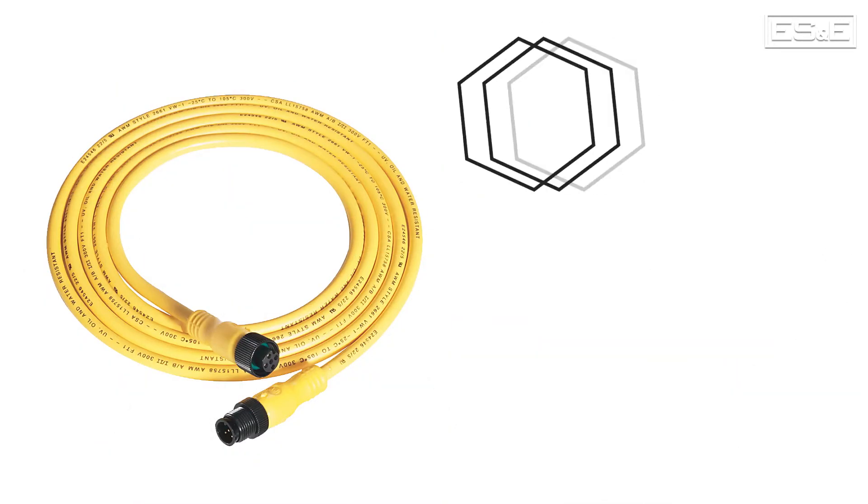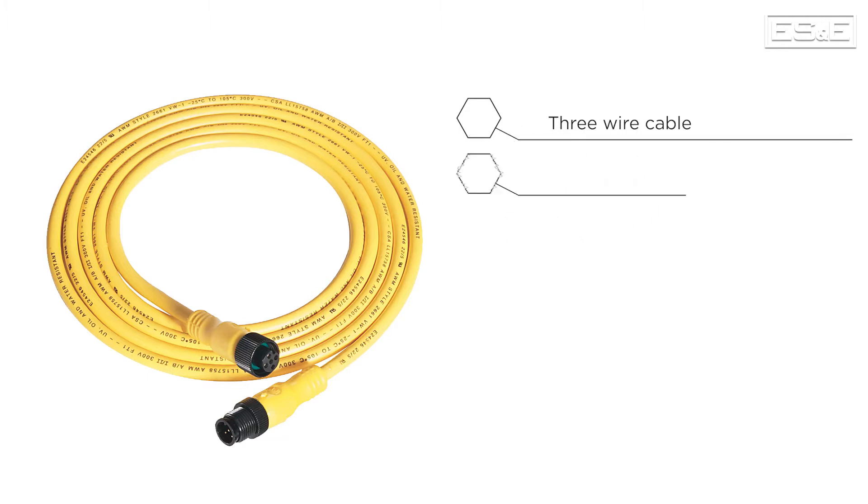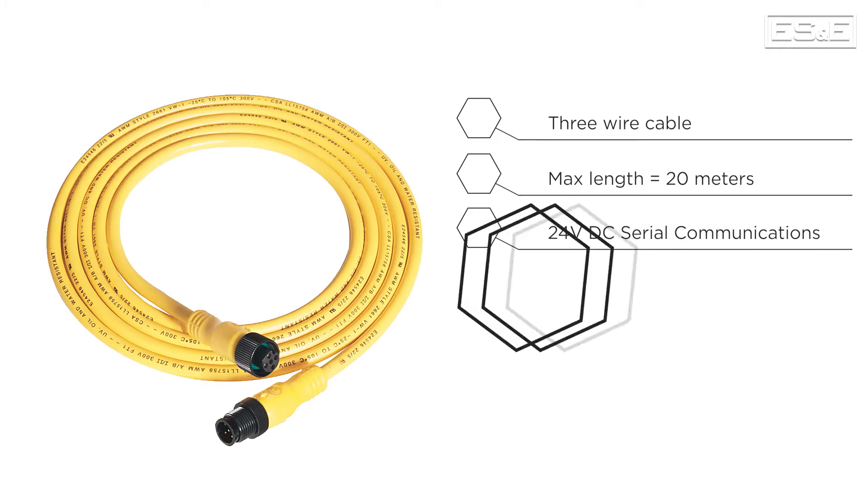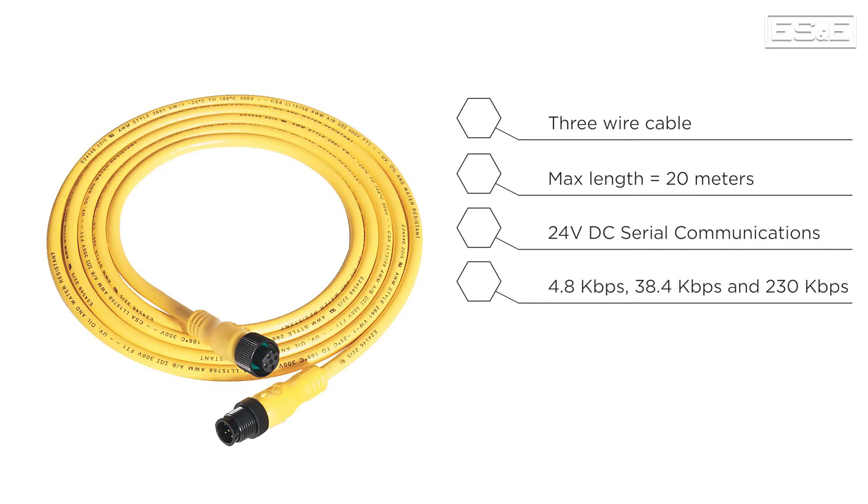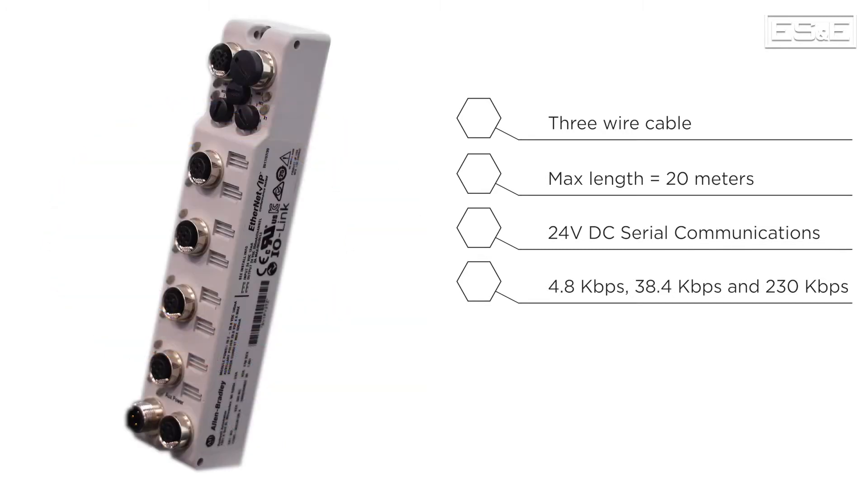The end device communications are established via a standard three-wire cable that is no more than 20 meters long. IO-Link utilizes a robust 24-volt DC serial communication system that transmits at three potential rates. The IO-Link Masters are capable of processing all three rates, and they are also capable of processing digital signals and analog values.